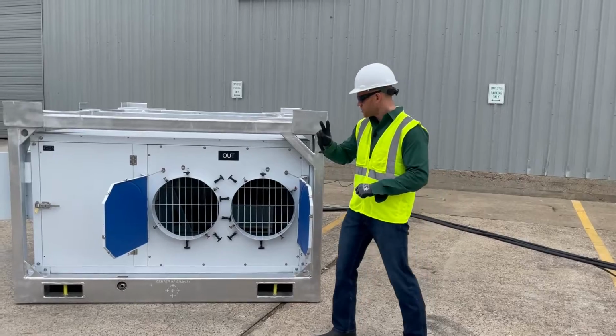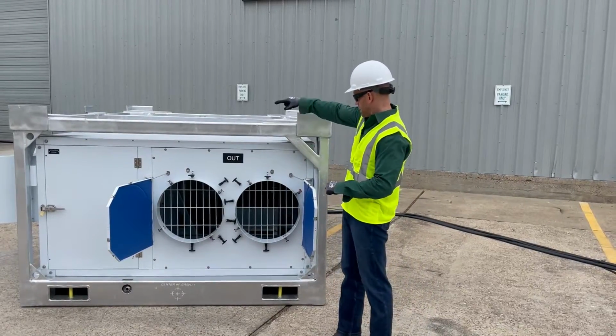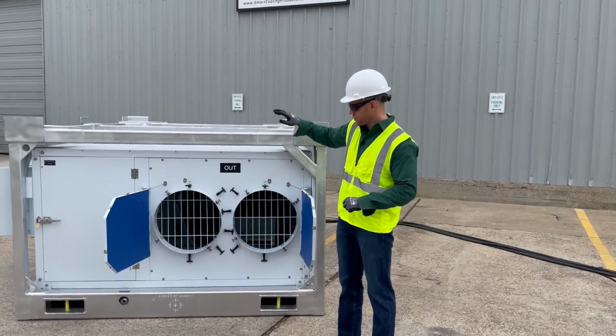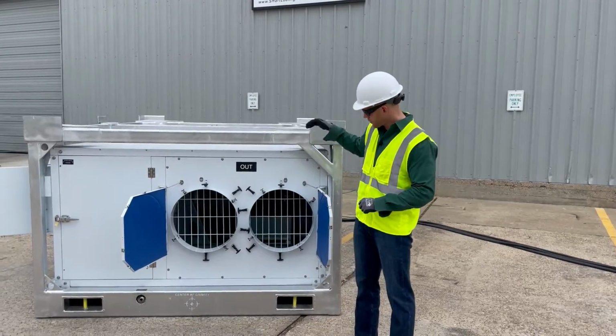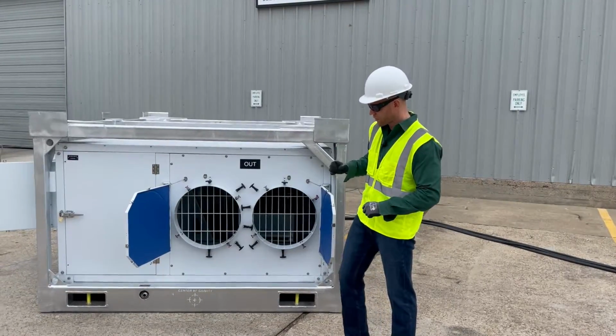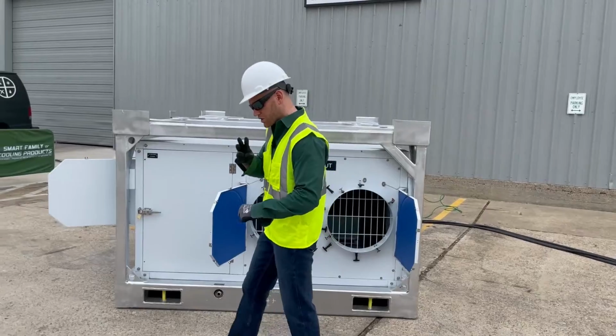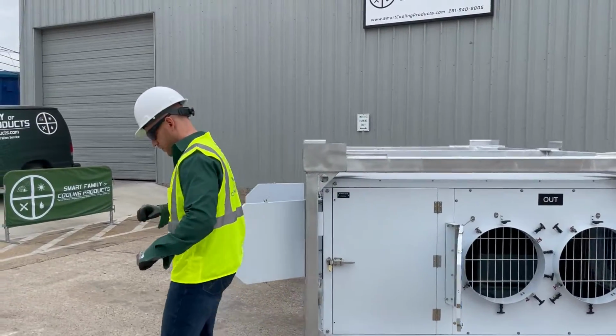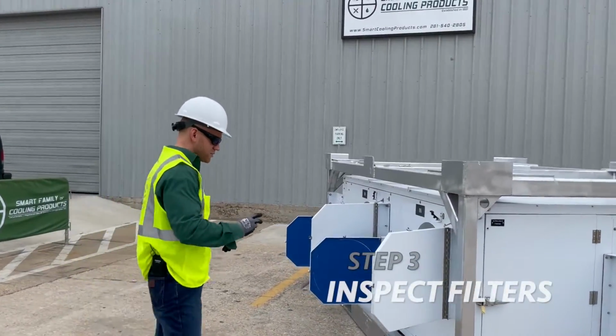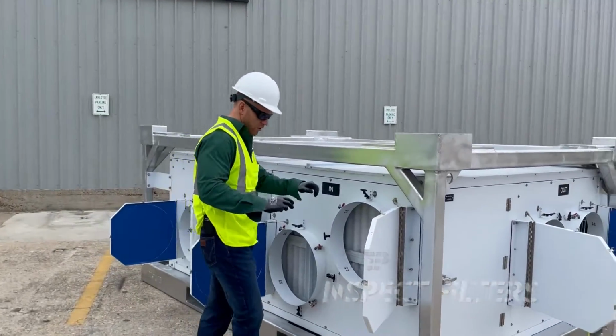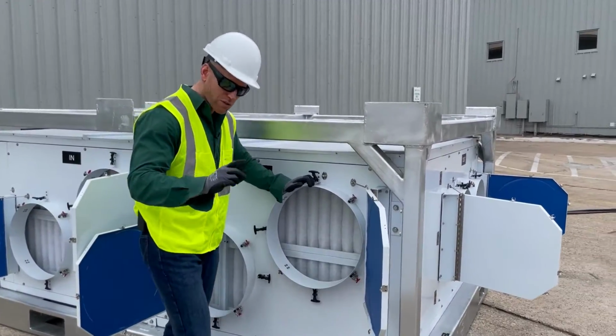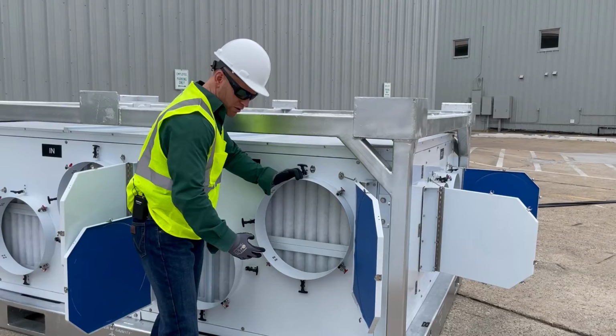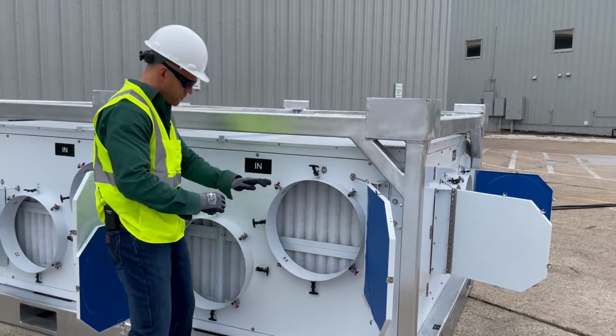All right? So step number 2, we have a clear path of air for this unit. We've opened up the correct amount of inlets and the correct amount of outlets or supplies. Step number 3 is we need to inspect our filters. We have inlet filters on all SMT model air handlers. There's 2 ways that we can inspect those filters. If we open up our return connections, we see we have nice access to all of our filters here.